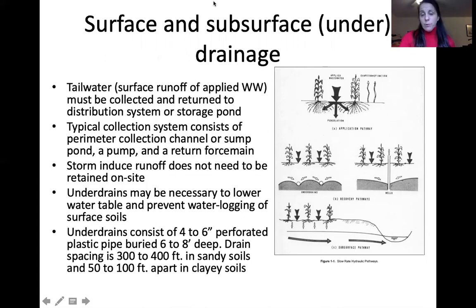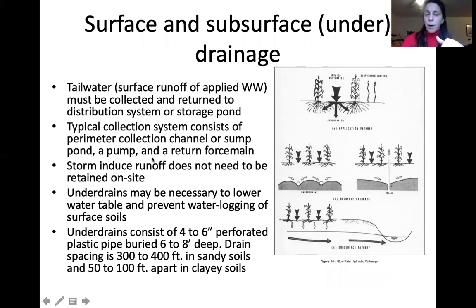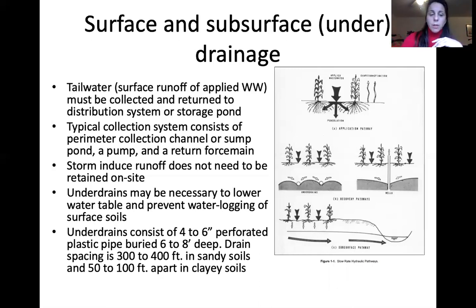Some systems incorporate under drainage — for example, Ohio croplands often have tile drainage due to wetland-adjacent areas with high water tables. During applications, a collection well or under drain may collect water, which is then reapplied via sump pump or pond. These are necessary to prevent waterlogging or groundwater impact. Under drains are typically 4- to 6-inch perforated pipes buried 6–8 feet deep, spaced about 300 feet apart in sandy soils and closer together in clay soils.